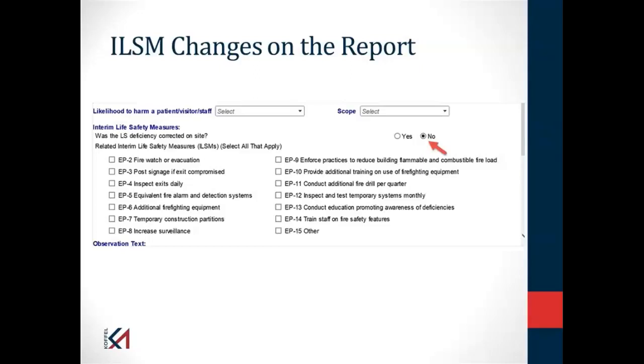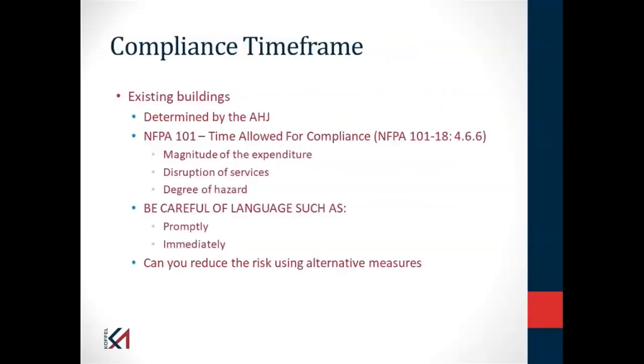I had a hospital one time with a fire alarm system problem, and because of the time it was going to take to correct that, we suggested that they go with a wireless system as a short-term, lower cost solution while they're installing or replacing the fire alarm system. So I'm not going to go through every one of those, but basically it forces me to evaluate, are there some things that I should do, again, with the intent that I'm going to reduce the degree of hazard that's associated with the risk or the non-compliant condition.